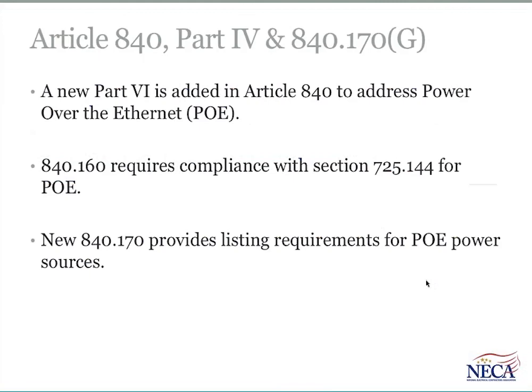And the last change, and we'll take some quick questions, and then Part 2 will be over. A new Part 6 has been added to Article 840 to address PoE, Power over Ethernet. That's a buzzword that you'll hear out there. Section 840.160 requires compliance with 725.144 for Power over Ethernet cables. New 840.170 provides listing requirements for Power over Ethernet sources. So we're going to see some evolution in this area.